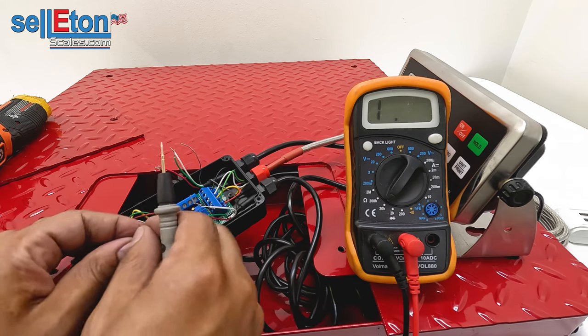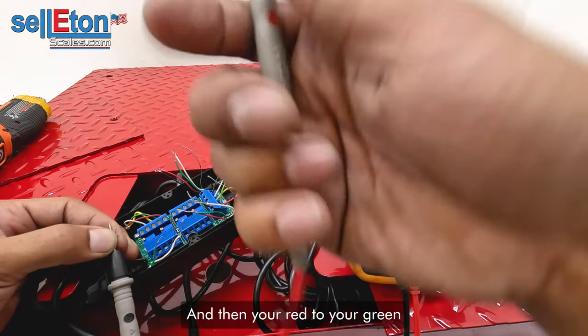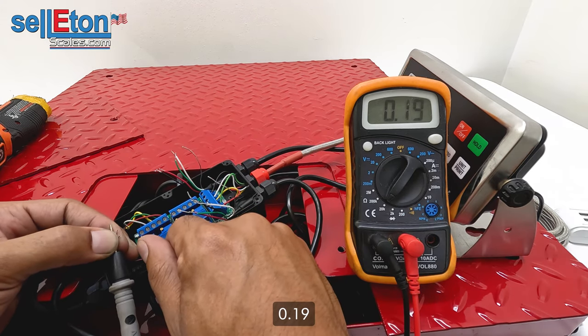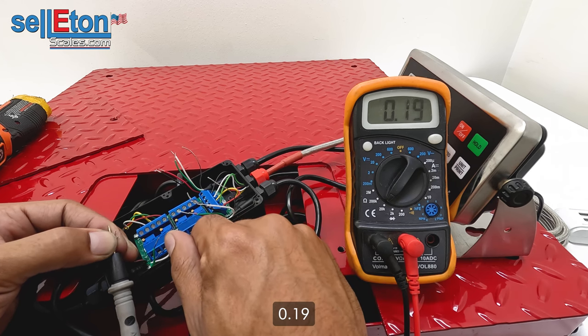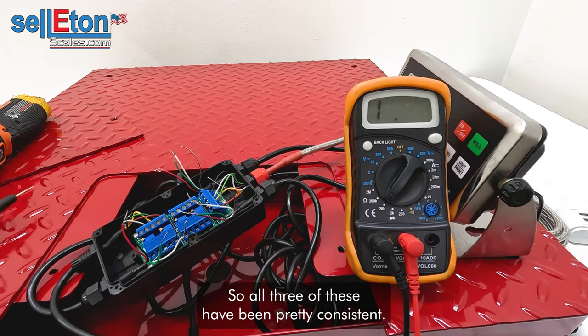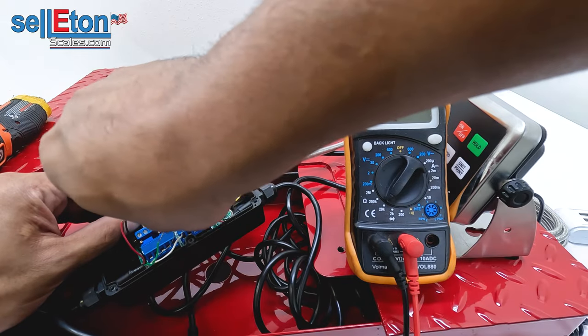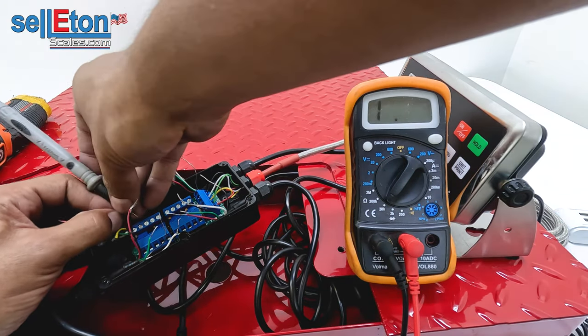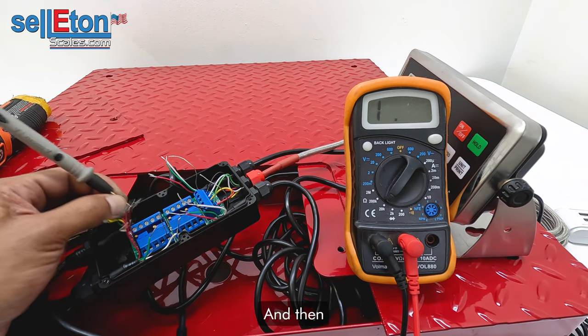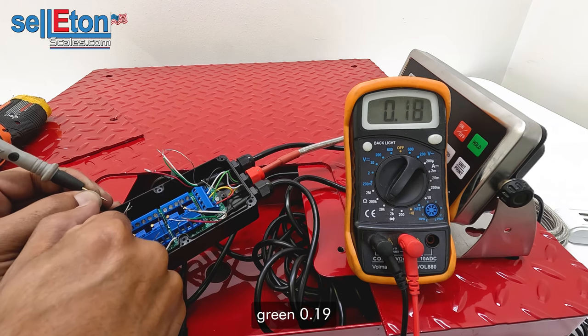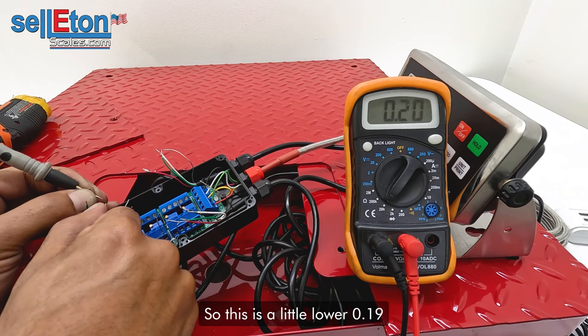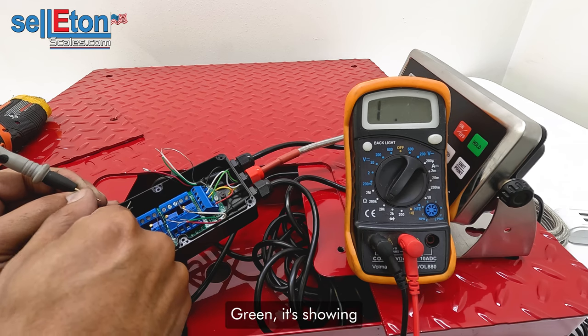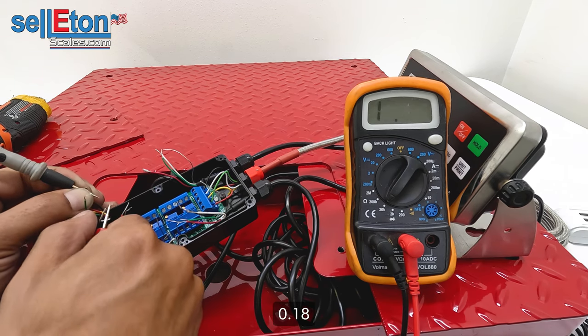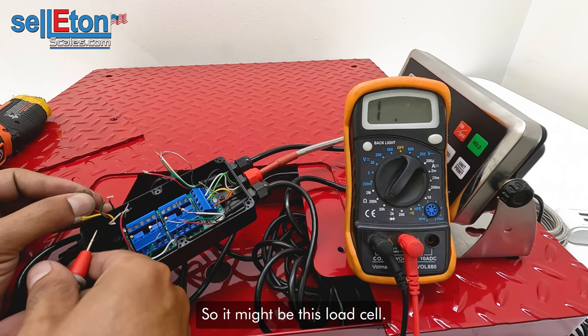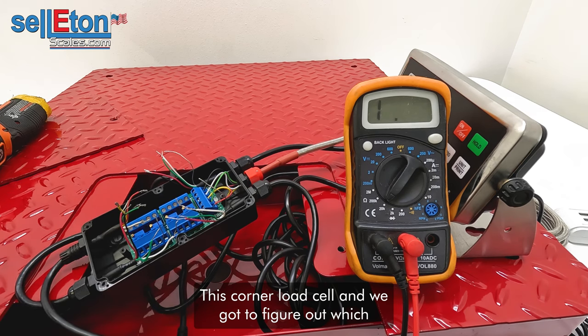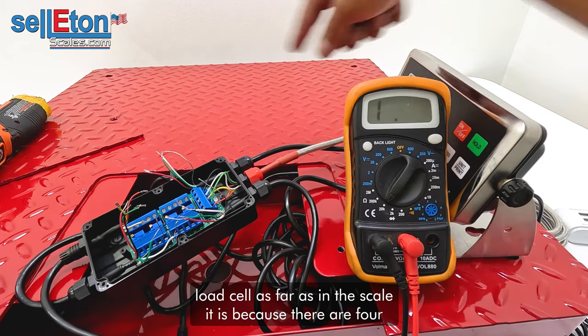Red and black here. And then your red to your green. 0.19. So all three of these have been pretty consistent. Let's take a look at this last one. And then green. 1.9, 1.8, 1.9. So this one's a little lower. 0.19. Green is showing 0.18. Sorry, 0.18, 0.19. So it might be this corner load cell, and we've got to figure out which load cell, as far as in the scale, it is, because there are 4.